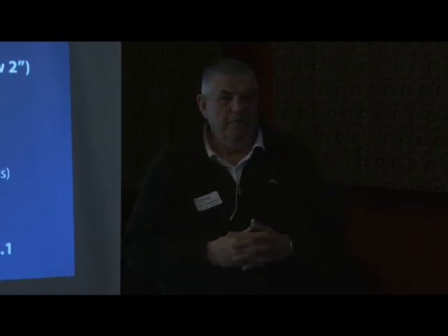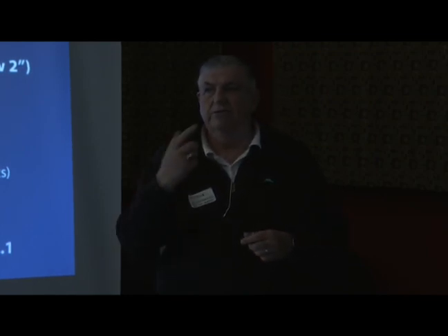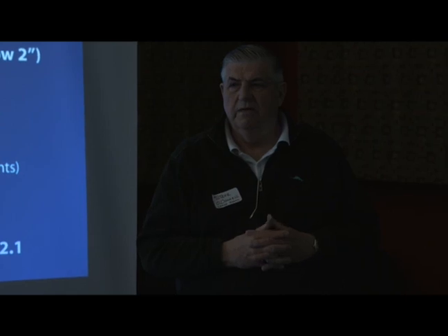And there are manual valves and there are automatic valves. The automatic valves are controlled in the control room. They can be turned off in, I think it says somewhere between 8 and 10 and 20 minutes. But that's really too late. But you can't shut them down faster because it would blow the line out. The manual valves can take up to an hour or two to get someone on site to do that.